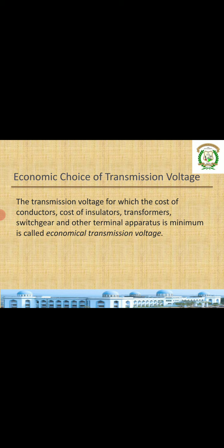Economic choice of the transmission voltage is nothing but the transmission voltage for which the cost of the conductor, cost of the insulator, transformers and switchgears and other terminal apparatus are minimum. That is called the economical transmission voltage. How to choose this one? First, the annual charge on the capital outlay is to be taken, as well as the annual cost of the energy wasted.